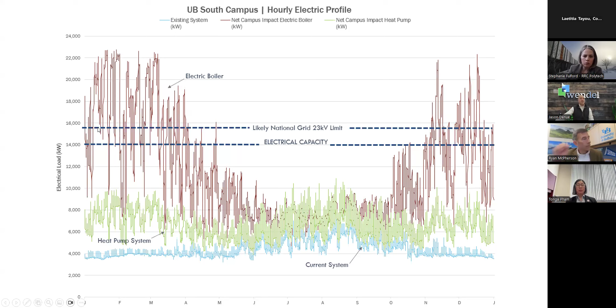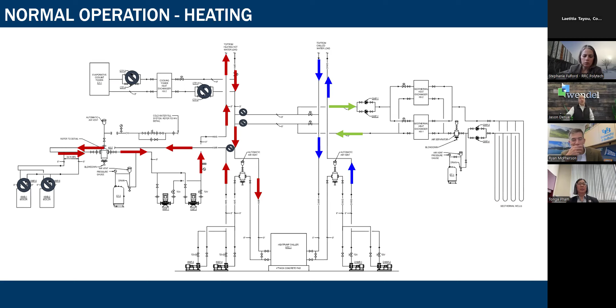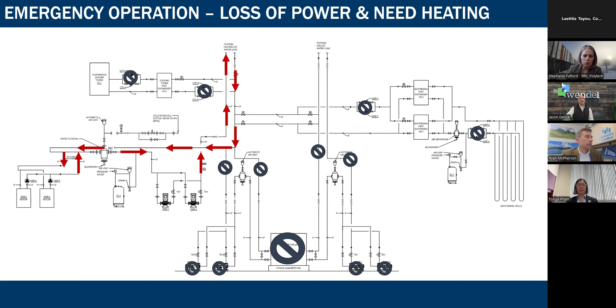Many of you may be asking, what about redundancy and resiliency? If I have everything on electric, what happens with my redundancy and resiliency? The idea is that under normal operation we would operate as a heat pump. When we had a loss of power, we would leverage condensing natural gas boilers to back up the system, and those natural gas boilers would be able to heat and provide energy to the system without the use of electricity.